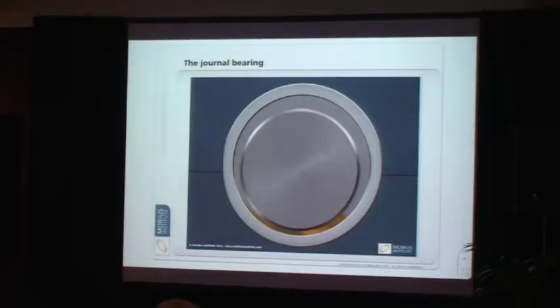Now, again I'm exaggerating the clearances and so on, but this is more like what it looks like. We've got that rotation, and in this case I'm not showing any motion of the shaft, but it forms a little oil wedge underneath, and that is what separates those two surfaces. It just sits on that oil, and as it spins you can see how it's sitting. It's critically important that we keep the lubricant up to the bearing - without it, we've got those two surfaces rubbing, which isn't good, as you can imagine. We can wipe the bearings, as it's called. Anyway, that's the situation going on inside the journal bearing - those are the measurements we want to take to see where it is, how it's moving, and whether it's all good.